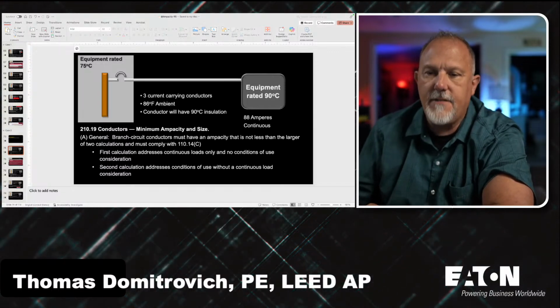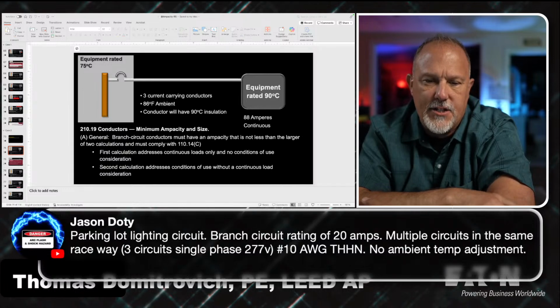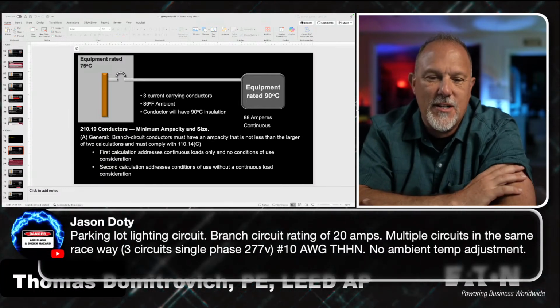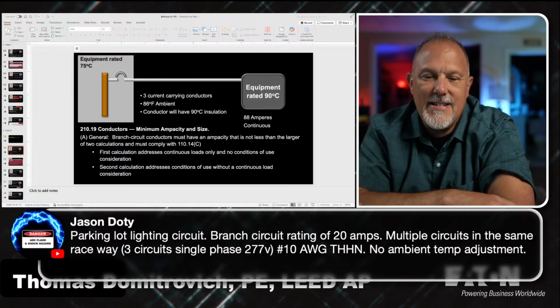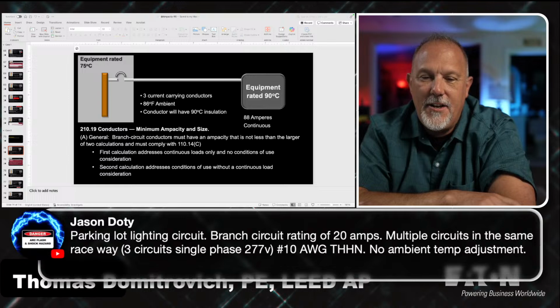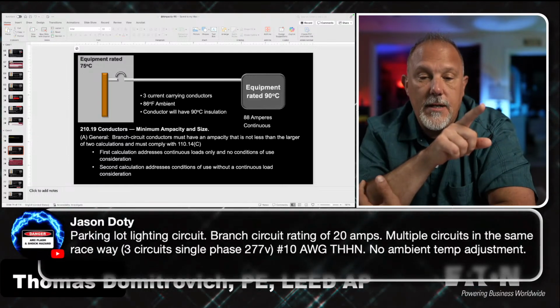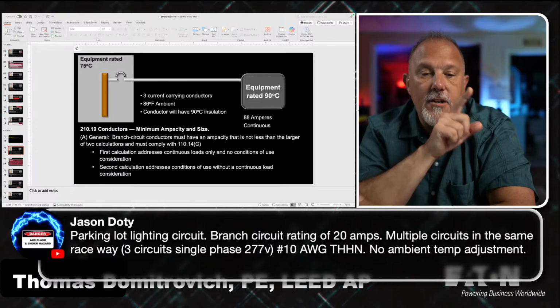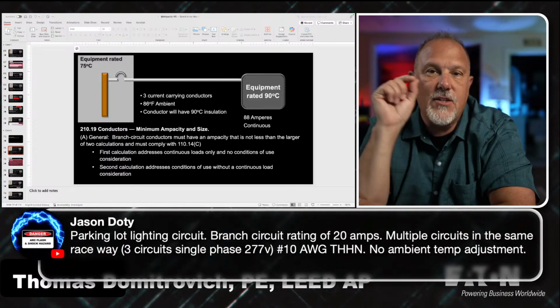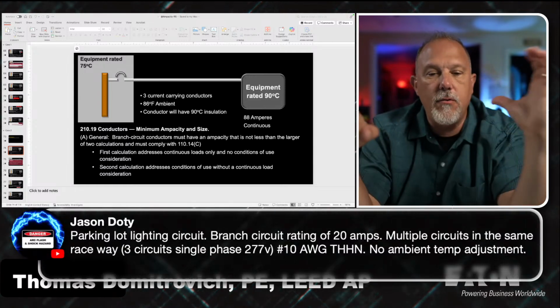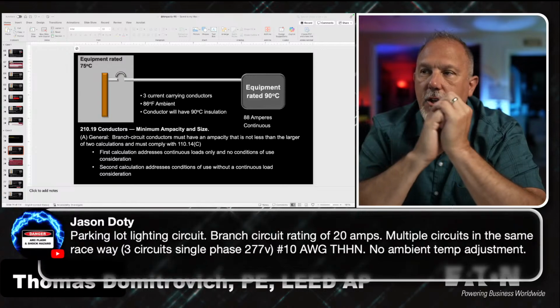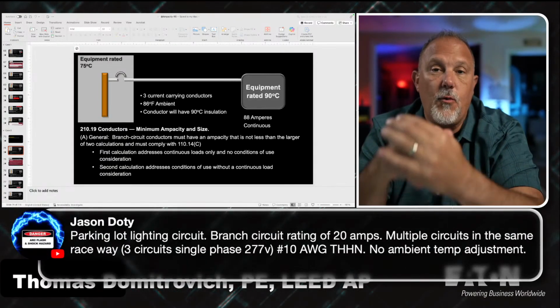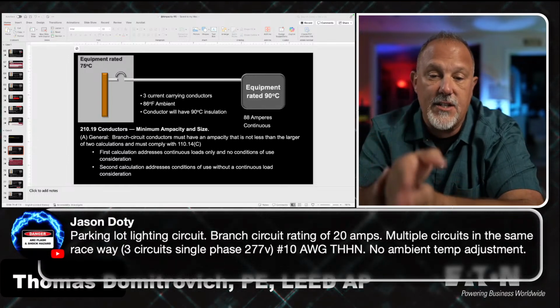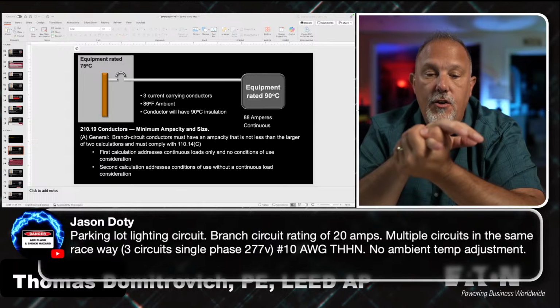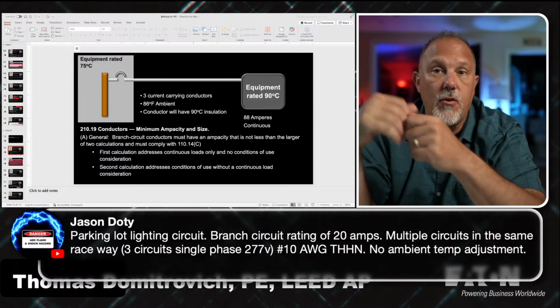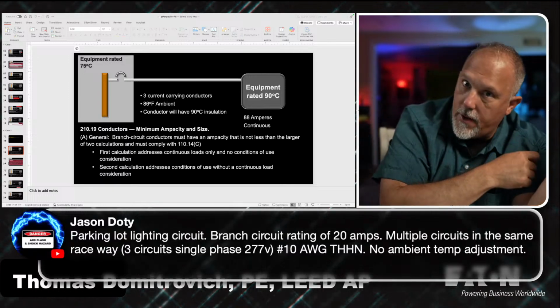Jason. What does Jason have to say? Jason says, parking lot lighting circuit. Branch circuit, 20 amps. Multiple circuits in the same raceway. 3 circuits, single phase, 277, number 10, no ambient temperature adjustment. So here's my issue. Here's what I need, Jason. What I need is what the load is, what the voltage is, and the fact that we're going to use a 90 degree C, or actually just give me the conditions. We'll pick the conductor and then we'll determine the conductor size. You went straight to a number 10 and whatnot. So I want to start with the load amps and work our way back up.